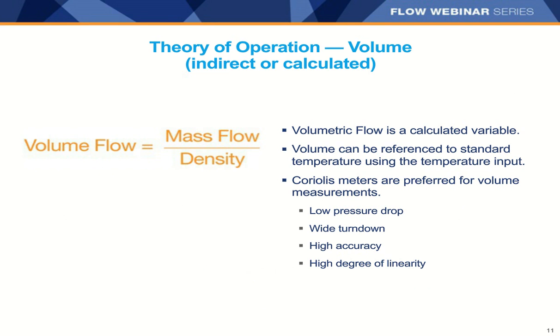Volumetric flow can also be calculated from a Coriolis meter. If you want flow in gallons per minute or liters per minute rather than kilograms per minute, volumetric flow is a calculated variable. The Coriolis meter measures mass flow and density, then divides mass flow by density to give calculated volumetric flow. Benefits include lower pressure drop, wider turndown, higher accuracy, and higher degree of linearity versus other volumetric flow meters.